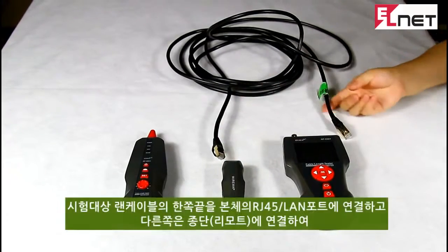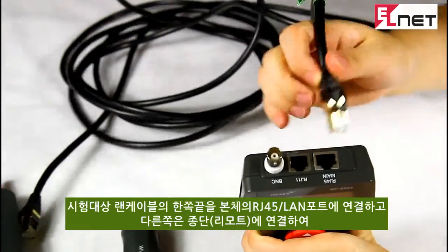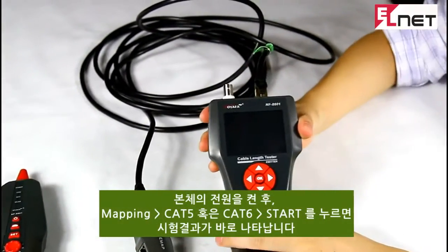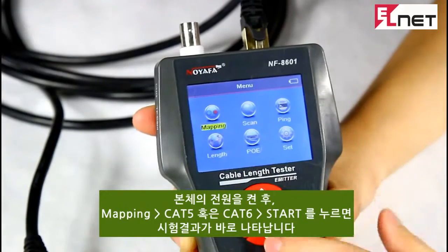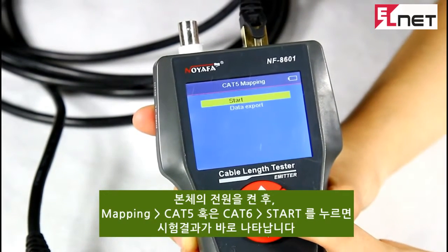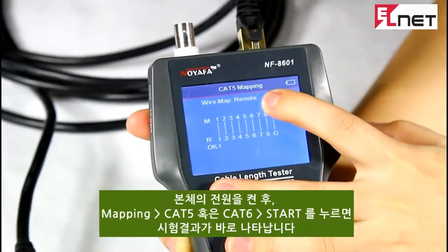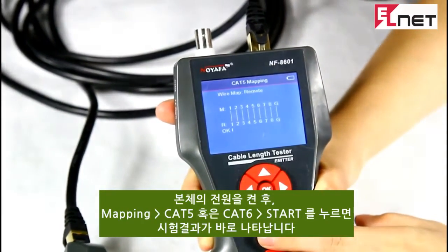Here I'd like to demonstrate remote testing with the main tester. Let's insert one end of the cable into the main RJ45 port, and the other end into the remote RJ45 port. Open the tester. Here we choose the wire mapping function from the menu and CAT5, then start testing. The result shows on the screen 1 to 1 until G to G, with a remote indicator in the top corner.